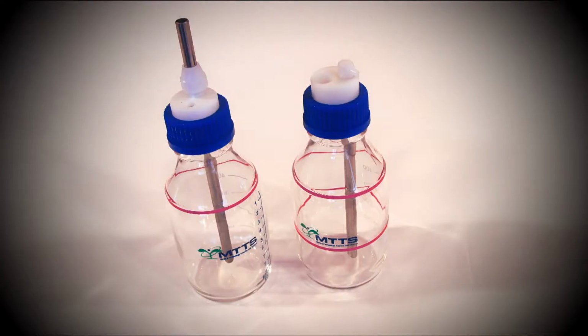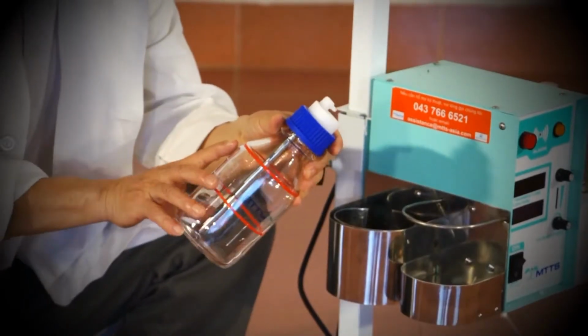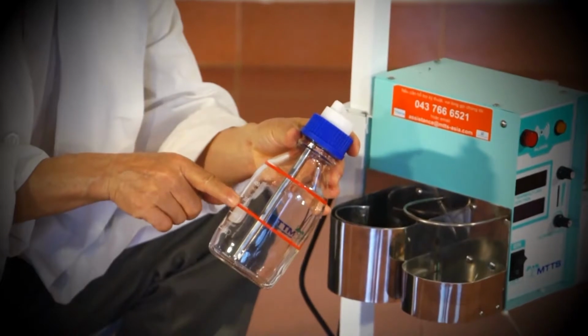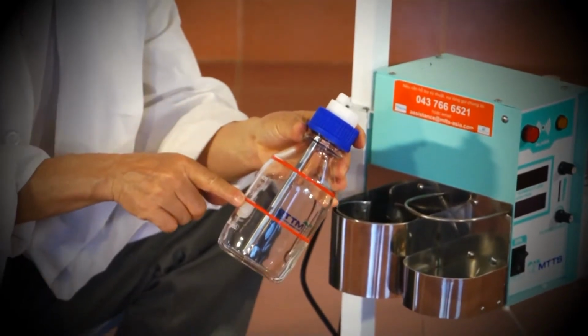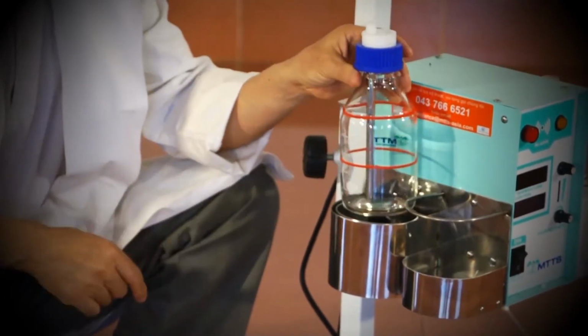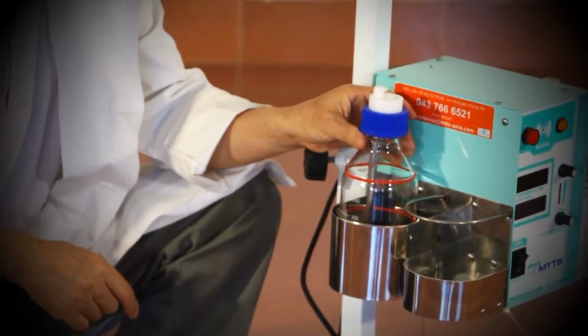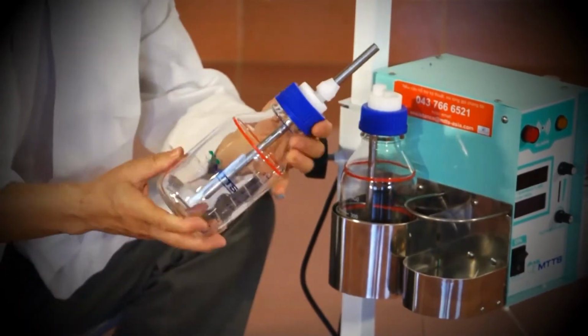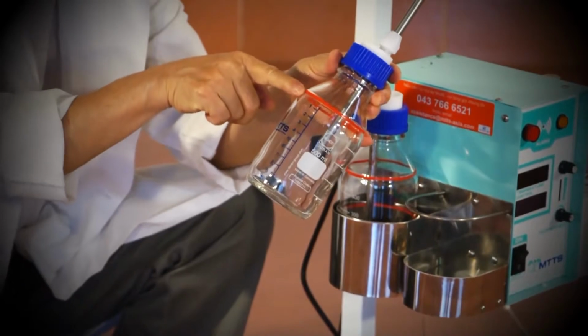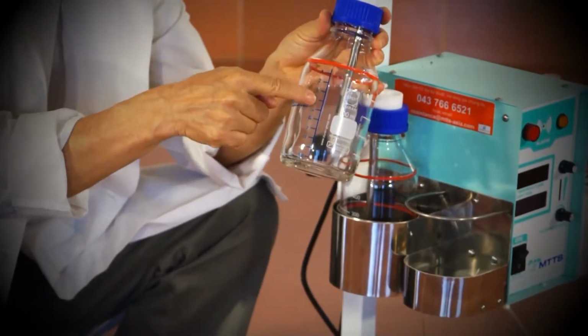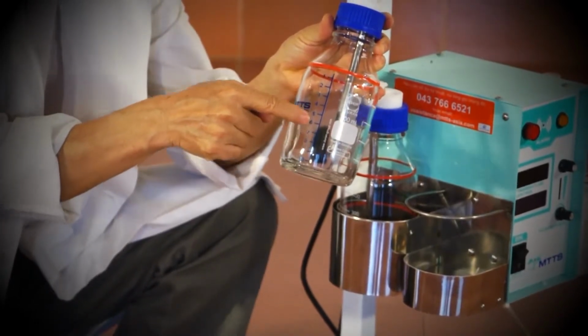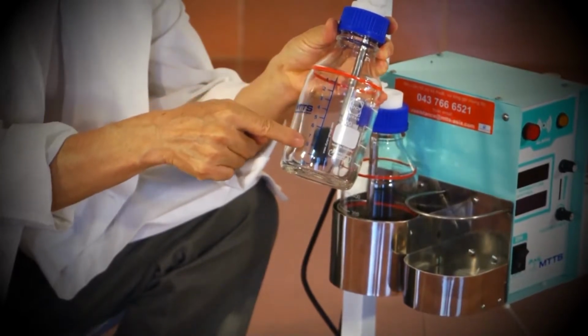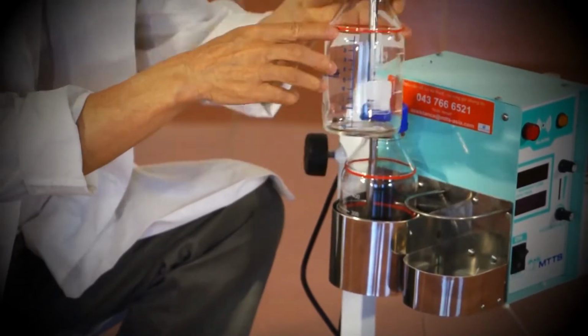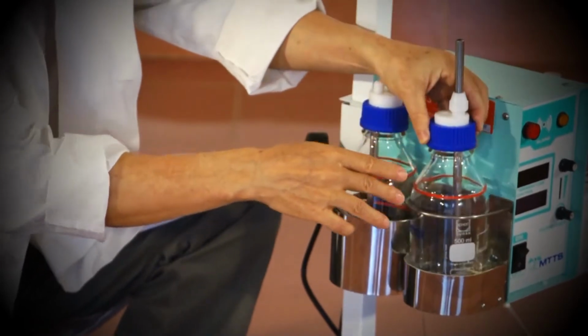There are 2 glass bottles used in this CPAP machine. The humidifier bottle has 2 red stripes indicating the range of allowed water levels. This is placed in the holder containing the heater. The PEEP bottle has 1 stripe indicating the required water level and a scale that indicates how much pressure the device is providing. This bottle is placed in the other holder.